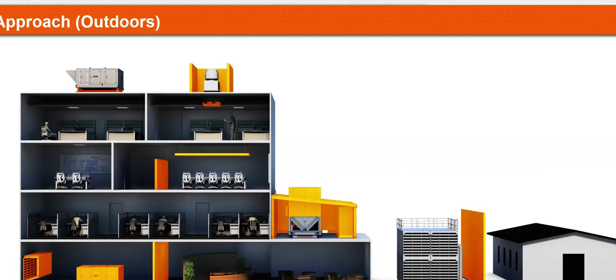Over the course of this webinar, we're going to focus a lot on custom solutions, starting with how to size panels at the bottom of a curb. In many cases, you don't have enough isolation below, and it's just sheet metal with insulation below. As you can imagine, some of the frequency coming out of the unit, if it's a bottom discharge curb, could be intrusive to the occupied space below.